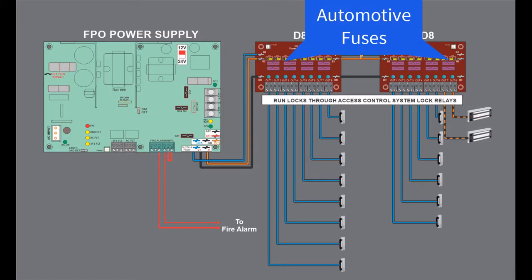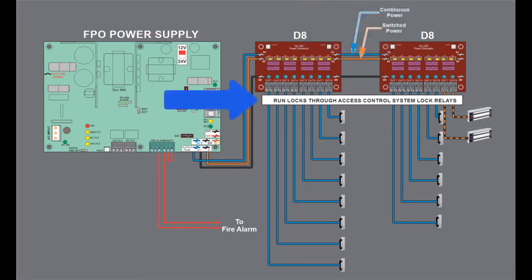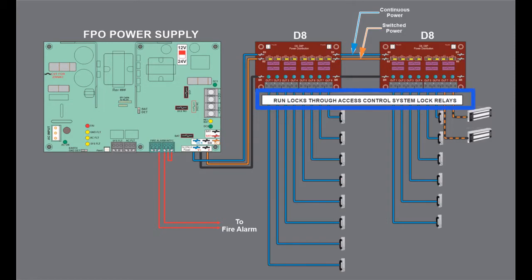Each strike now has a fuse in series with it and can be controlled by the access system door relays. Each mag lock also has a fuse in series with it and can be controlled by the access system, but will drop out when the fire alarm interface of the FPO is activated by the fire alarm panel.